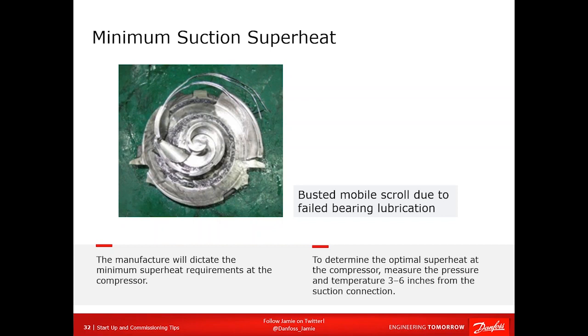Well, this is what happens to the scroll when you lose lubrication in the system. When that bearing seizes, do you think that scroll is going to stop at 1800 RPM or whatever? No, it's got a massive counterweight. It's going to keep going until it screws the mobile scroll into the fixed scroll. And even then, it's going to keep going until it smashes the heck out of everything inside. So when you pick the compressor up and shake it, it sounds like a piñata. That's not a good sign. And when you cut it open, this is what you find.